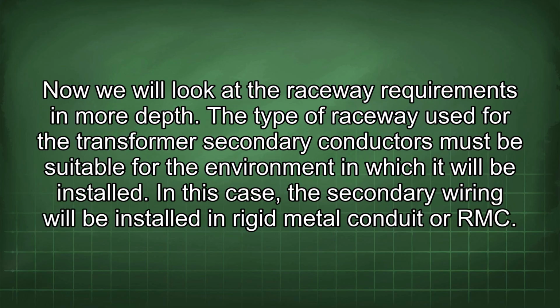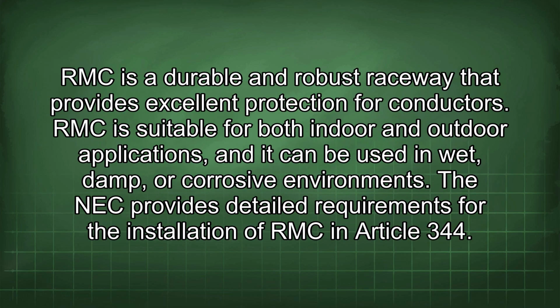Now we will look at the raceway requirements in more depth. The type of raceway used for the transformer secondary conductors must be suitable for the environment in which it will be installed. In this case, the secondary wiring will be installed in rigid metal conduit or RMC. RMC is a durable and robust raceway that provides excellent protection for conductors. RMC is suitable for both indoor and outdoor applications, and it can be used in wet, damp, or corrosive environments. The NEC provides detailed requirements for the installation of RMC in Article 344.